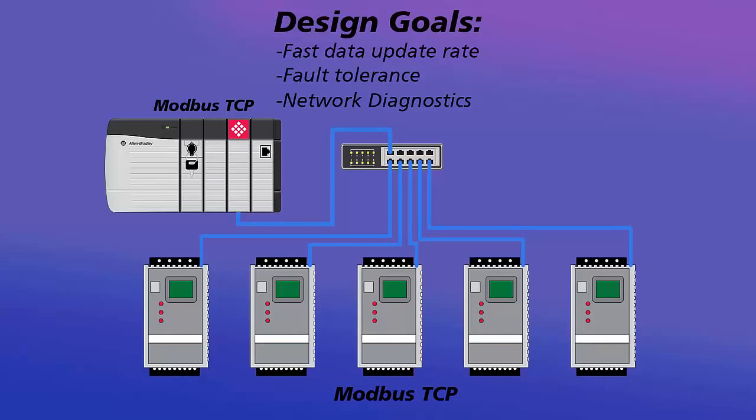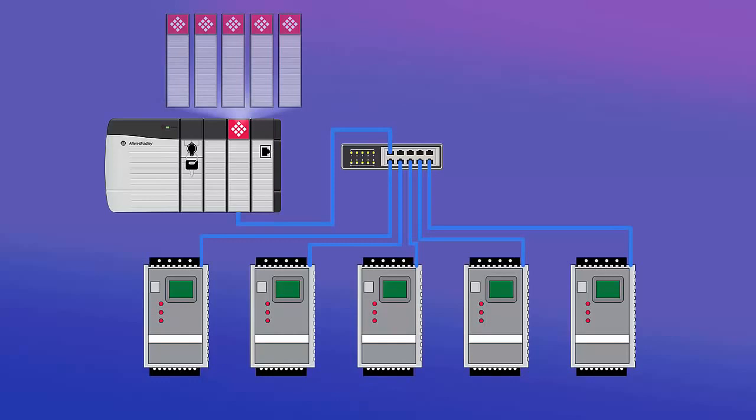The ideal situation here would be to use a communication module that supports multiple clients, one talking to each of the servers. This will ensure faster communications by giving each drive a dedicated connection to a Modbus TCP IP client. Commands can be sent to all 5 drives by separate client connections instead of cycling through each drive one at a time. In the event of a drive going offline, communication with the other 4 drives will remain unimpeded.